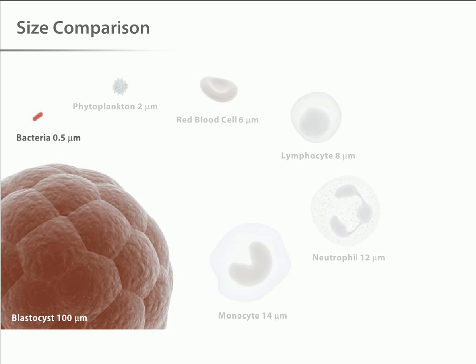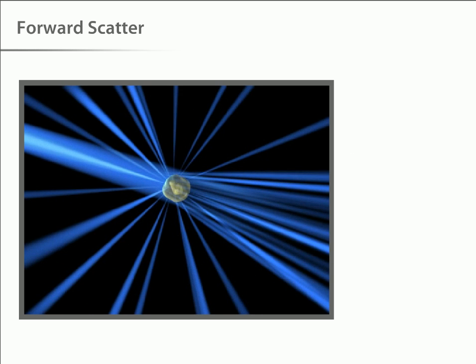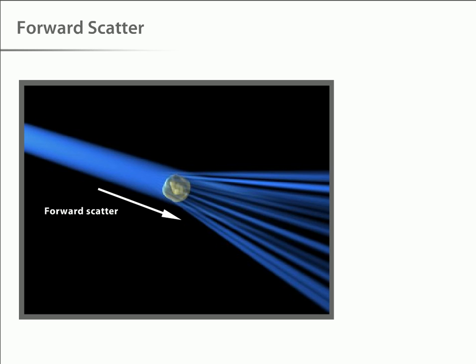Now let's see how laser light is used to detect individual cells in the stream. As a cell passes through the laser, it will refract or scatter light at all angles. Forward scatter or low angle light scatter is the amount of light that's scattered in the forward direction as laser light strikes the cell. The magnitude of forward scatter is roughly proportional to the size of the cell, and this data can be used to quantify that parameter.